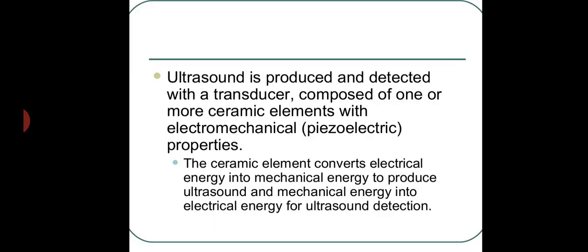Ultrasound is produced and detected with a transducer composed of one or more ceramic elements with electromechanical properties. The ceramic element converts electrical energy into mechanical energy to produce ultrasound, and mechanical energy into electrical energy for ultrasound detection.